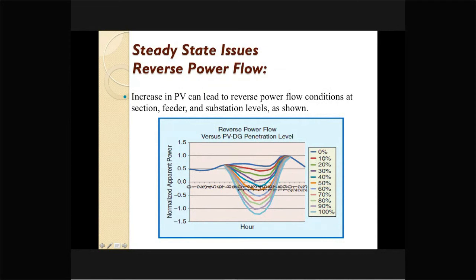Now, when you go on increasing the PV integration, after a certain point you can see that it goes negative. So when the integration becomes around 40%, it goes negative for some of the time of the day. This says that if the PV penetration is higher, you will end up with a reverse power flow, and that will go on increasing further and further. And the neck of the duck will become very large, and you need a large ramping of power when you go for a larger penetration of photovoltaic power into the grid, and that also will increase the amount of reverse power.